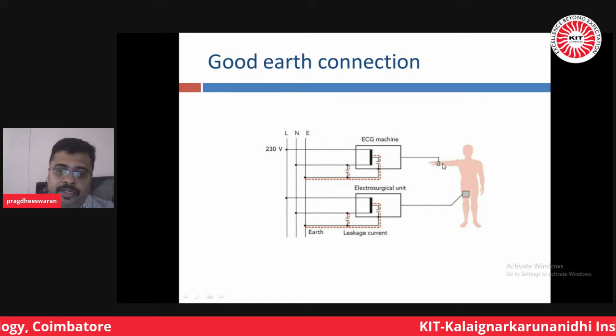Every equipment has got a proper insulation. Medical equipment, I'm saying, every equipment has got a proper insulation, and we follow certain insulation standards which will collect all the equipment leakages, of a magnitude close to around 100 milliampere, and terminate them to the electrical main earth wire, so that wherever the least resistance path is there, the current follows the least resistance path to get a drainage, right? We call it leakage drainage. Then the patient who is touching the machine will not get the current, or it will be minimized.